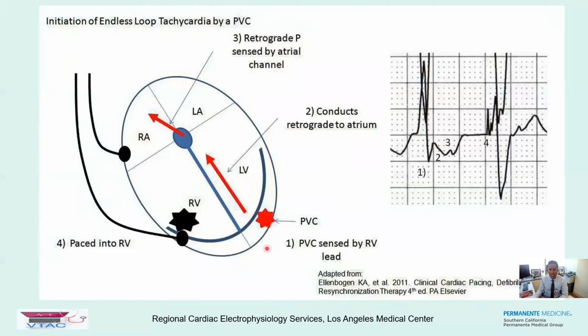Well, what if there's some kind of rhythm like a PVC that goes back to the atrium? This sees the A, that tells the V to pace, and that goes back to the A, because sometimes you can have VA conduction, and you get into what's called an endless loop. So that's pacemaker-mediated tachycardia. Both of those can happen, and you have to change the pacemaker into a non-tracking mode, which will then break the vicious cycle - change it to like a non-tracking mode, almost a single chamber pacemaker, and then it won't track the atrium anymore.